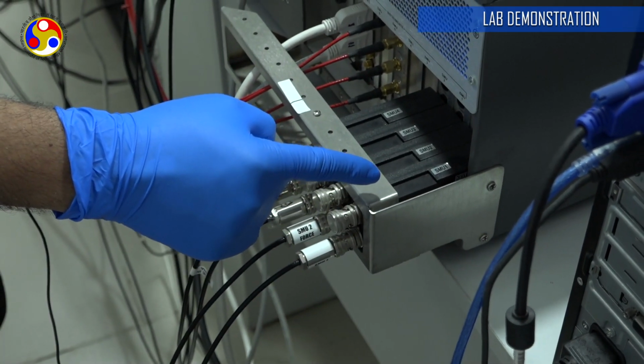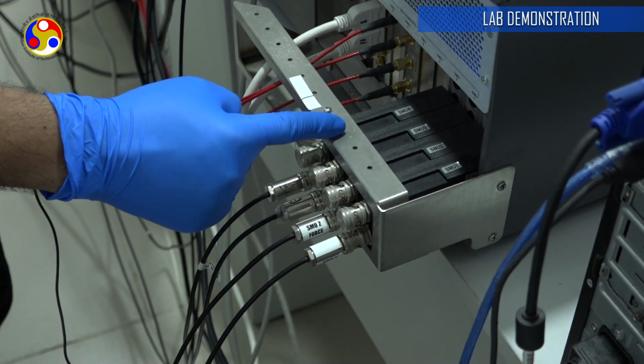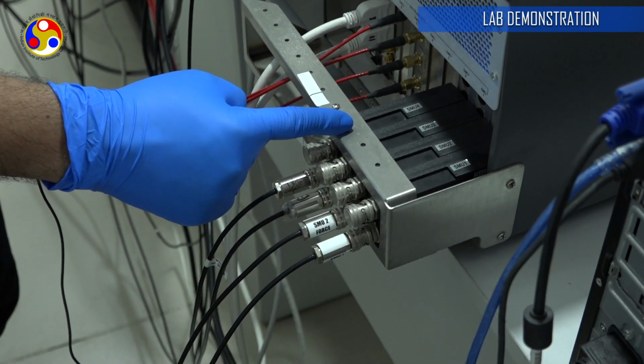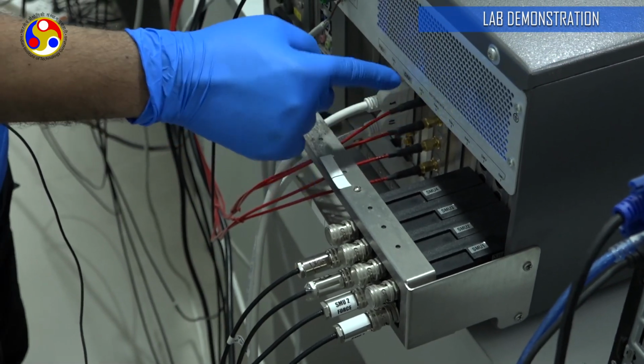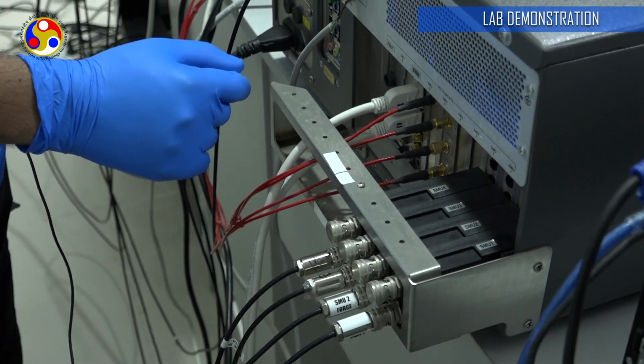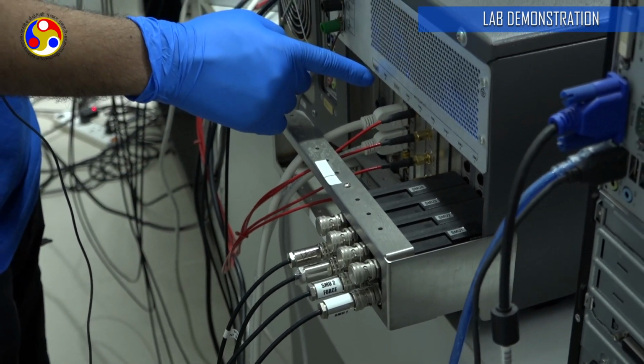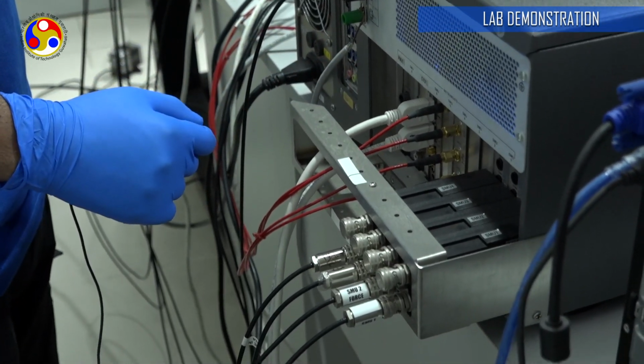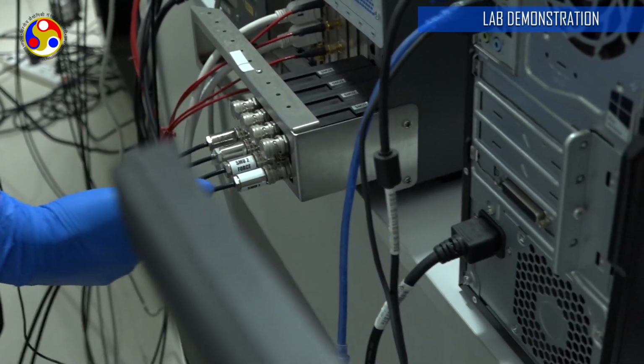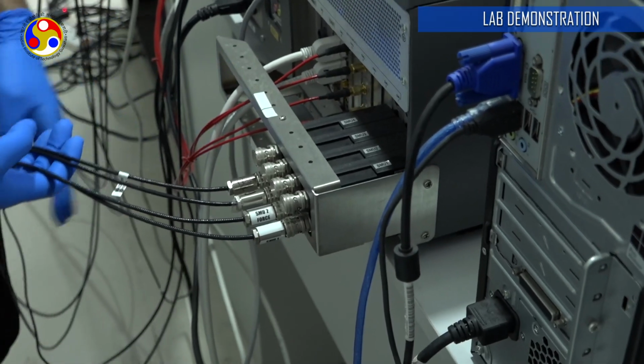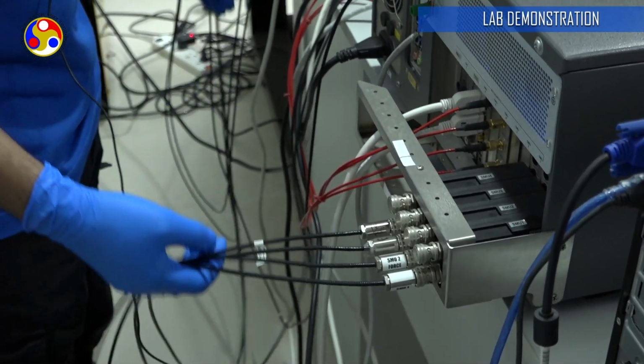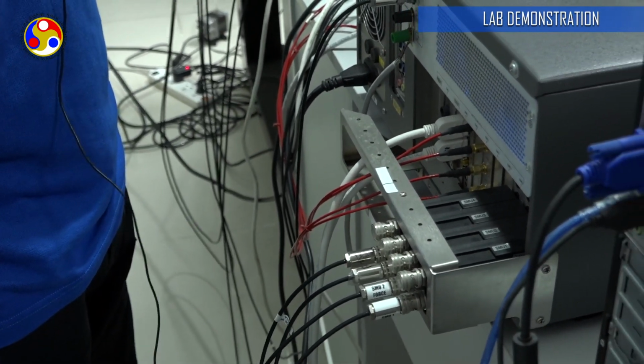So these are the four SMUs, SMU 1, 2, 3 and 4. These are for IV measurement. This unit here is the capacitance voltage unit for CV measurement, and this unit, the PMU, is the pulse measure unit. As you can see, these units are connected via triaxial cable to the probe station.